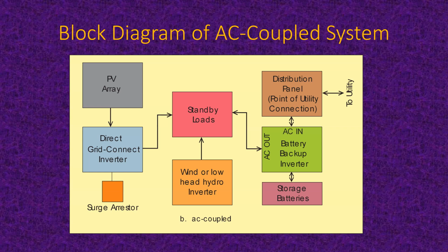So in this particular case, when the sun shines, the electricity goes to the direct grid connect inverter, some of which are approaching the 99% efficiency level these days, whereas the battery backup inverters tend not to be quite that high, more like 95% efficient. So that's really significantly less loss. If you go straight direct grid connect to standby loads, those loads are getting some pretty efficiently generated electricity. That same standby load panel could have some additional electric feed from wind or low head hydro. And if the utility is up, the part of the system on the right-hand side still works the same as the previous picture.